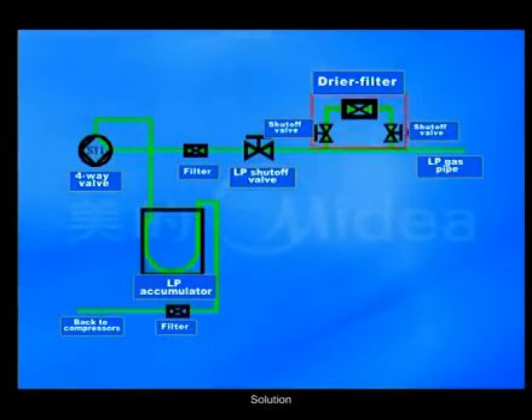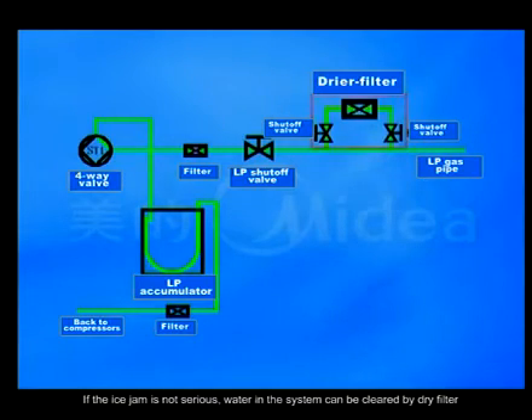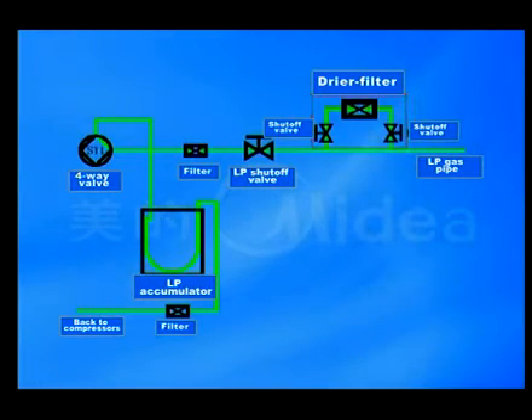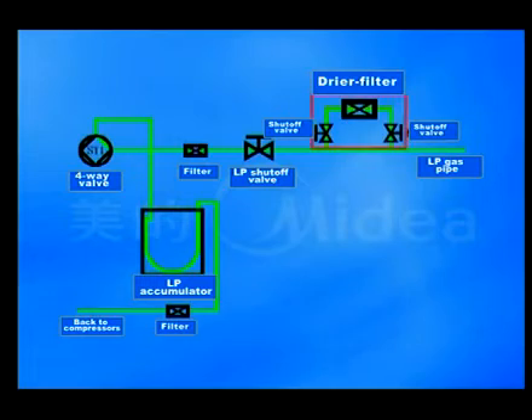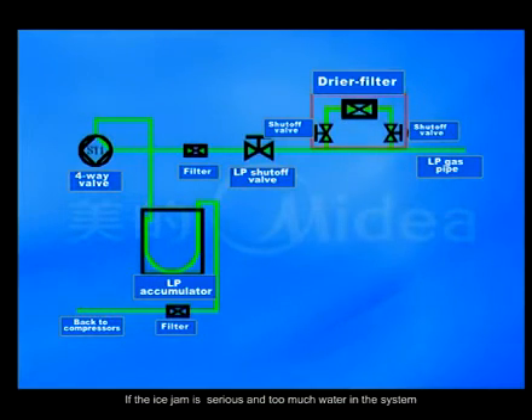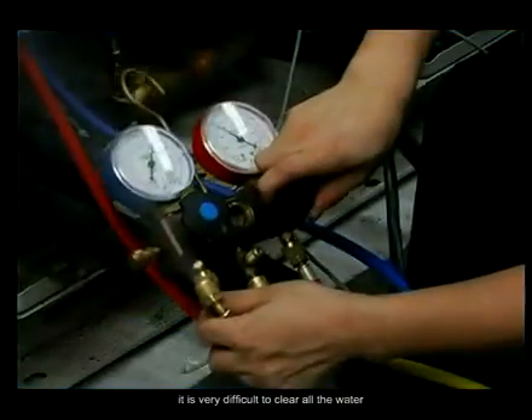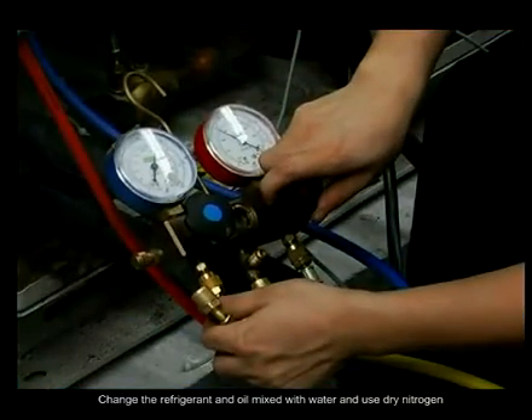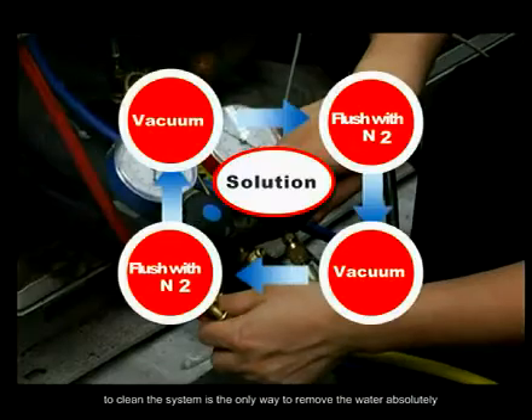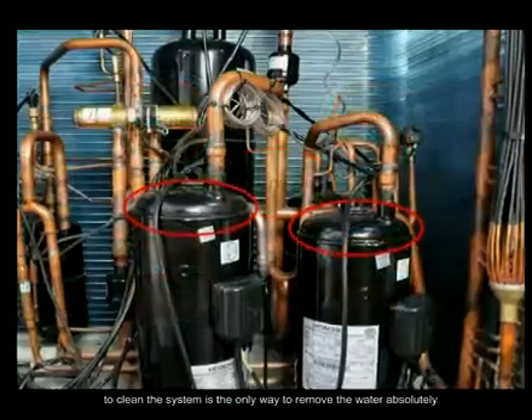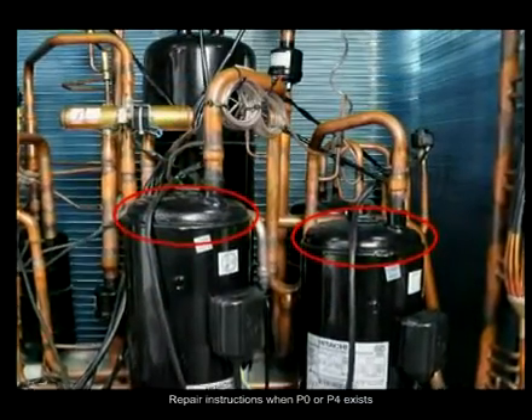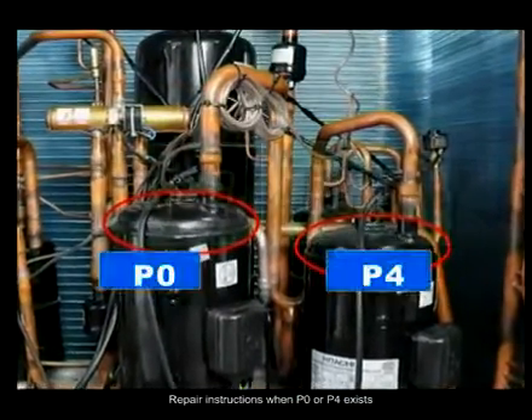Solution: if the ice jam is not serious, water in the system can be cleared by a dry filter. If the ice jam is serious and there is too much water in the system, it is very difficult to clear all the water. Changing the refrigerant and oil mixed with water and using dry nitrogen to clean the system is the only way to remove the water absolutely. Repair instructions when P0 or P4 exists.